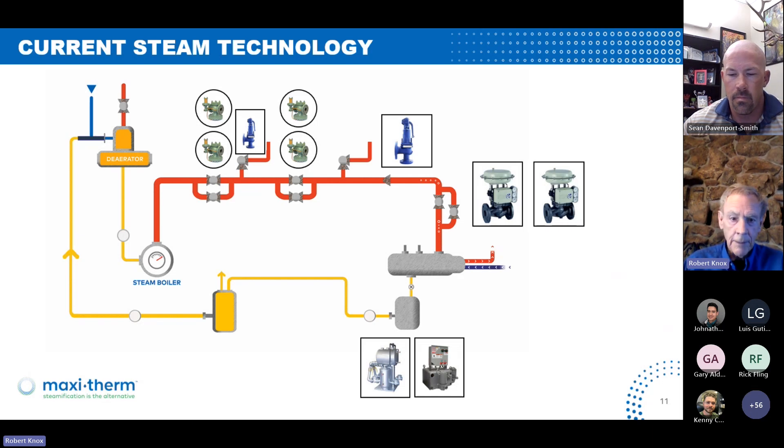Problems encountered would be on the PRVs: you have orifices, and you have that sensing line that can be done wrong — you have pilot leaks or main valve leaks. On the steam control valves of the heat exchanger, you can cut your seat. On the pumps: electric pump — you can lose your seals; pressure motive pump — you won't get the cycles that you'd like necessarily. From the pressure motive pump, you go to a receiver right here, and then up back to the DA and back to the boiler.